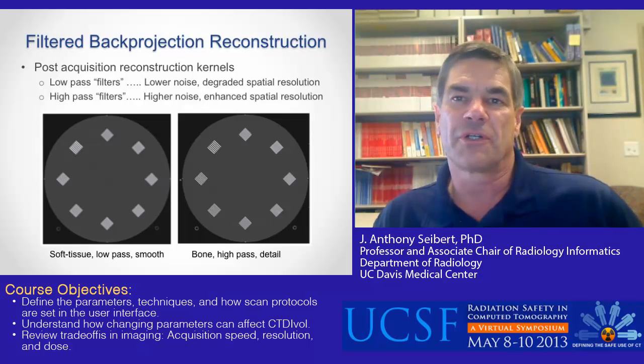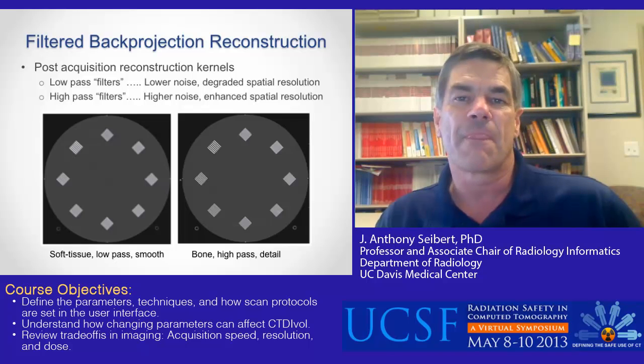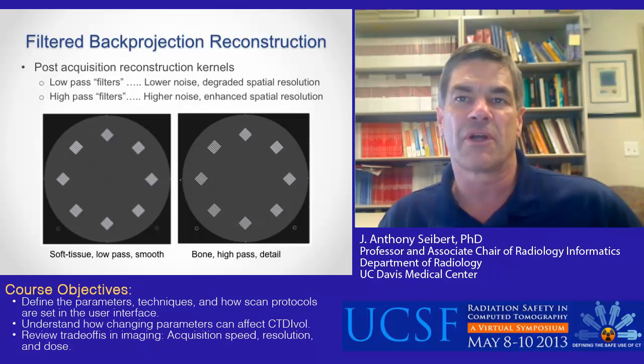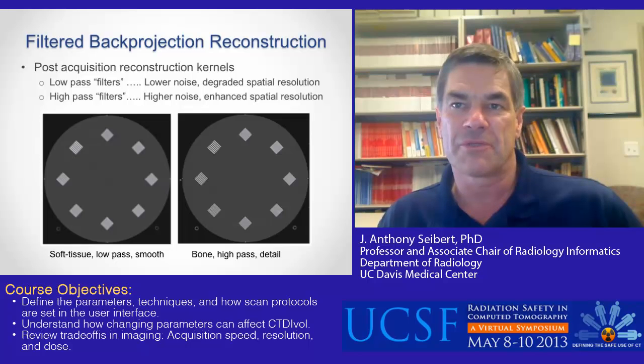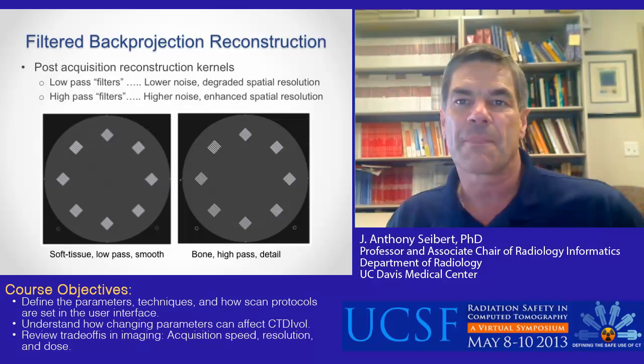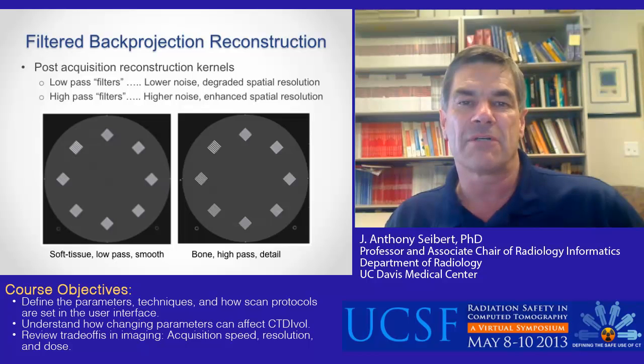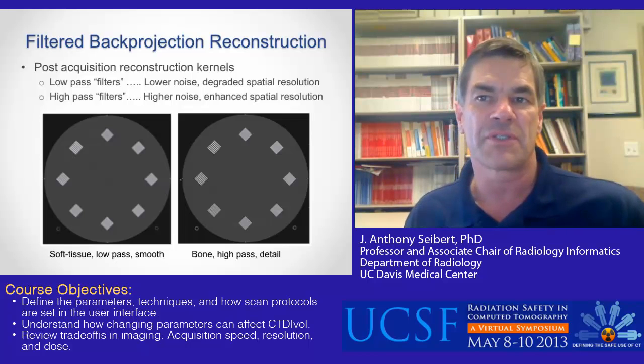Reconstruction filter kernels do not directly affect dose, but spatial and contrast resolution are both affected. A low-pass smoothing filter creates an image with less noise and improved contrast resolution of large objects, but a loss of detail, as shown by a high-resolution detail phantom. A high-pass detail filter provides enhanced spatial resolution, but greater emphasis of noise and less contrast-to-noise ratio.